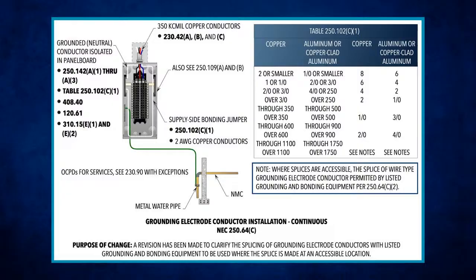So I'm coming up and I'm making my connection with all these different conductors coming up there. And now I'm asking you here, how can I put a number 8 on that if I'm interconnecting all these electrodes when it doesn't tell me I can do that with a number 8? Yeah. 100%. It's very simple. And this is why I like people to watch and pay attention to what's being said on here. You don't have to take my word for anything. I'm giving y'all all the sections. Go read them and see if it doesn't state that. Now, if I can't do it there, why the hell am I all of a sudden allowed to do it for something else? Yeah, 100%.